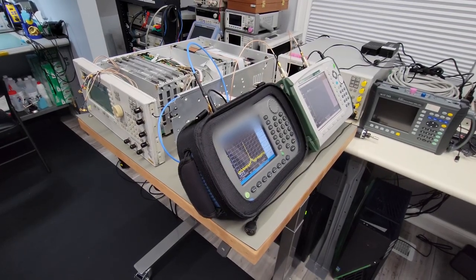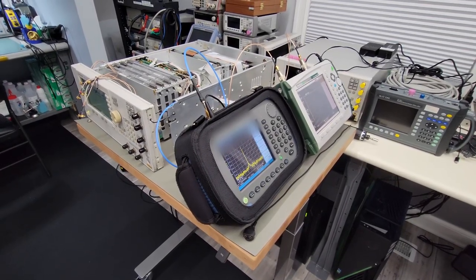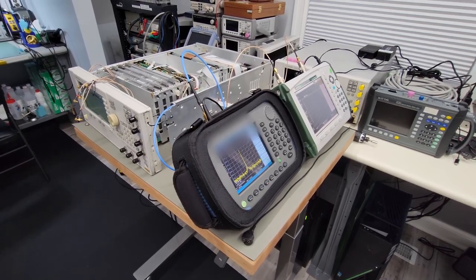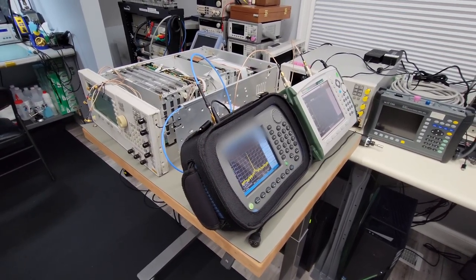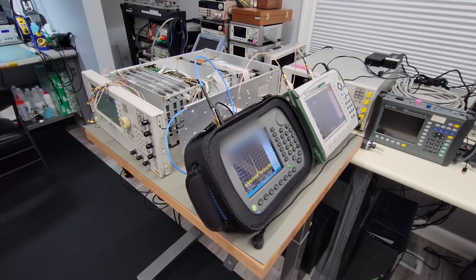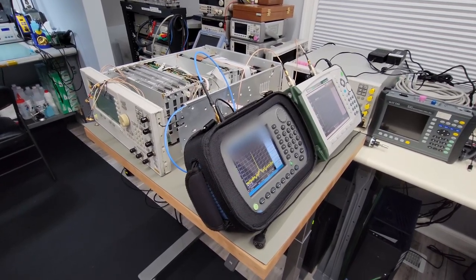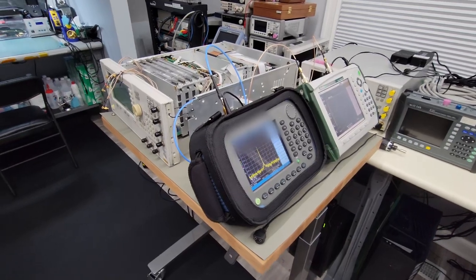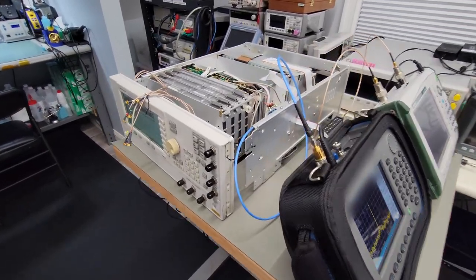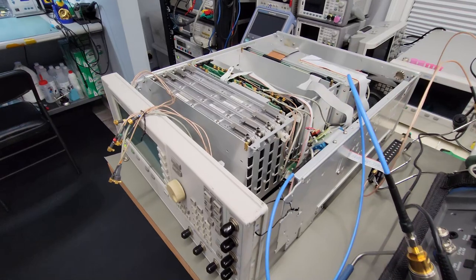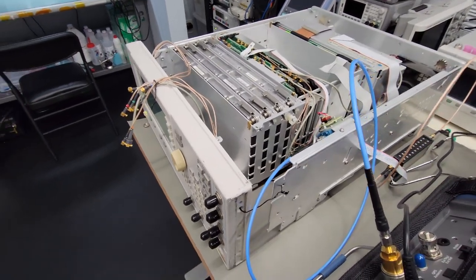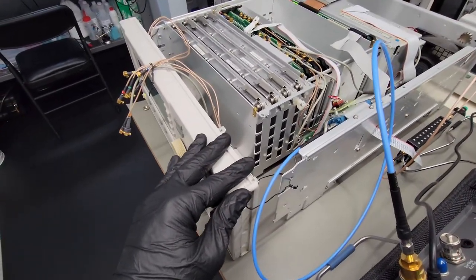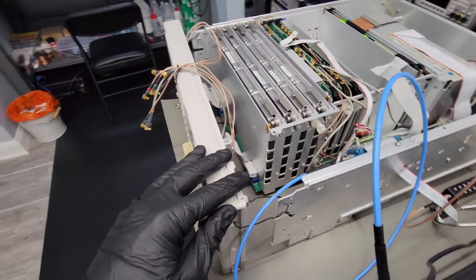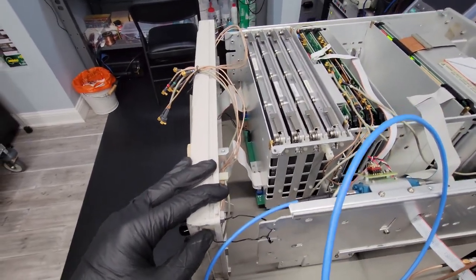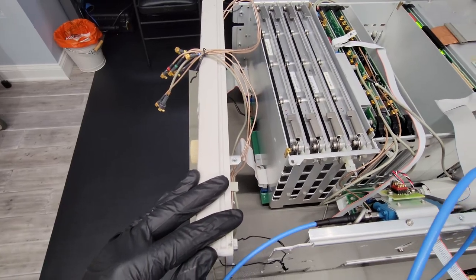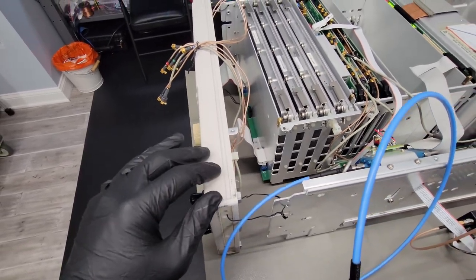All right, so now that we've dealt with the mechanical issue with the damaged front panel connector, we can move on to the RF testing of the instrument and beginning to troubleshoot the actual problem that it has. So this is my test setup here, and this will allow me to power on and test the instrument at different points within the instrument. So while the front panel is disconnected, this actually makes my job a little bit easier. You can see that it's not mechanically screwed into the chassis. I just have the digital connections hooked up here so that we can operate the instrument.